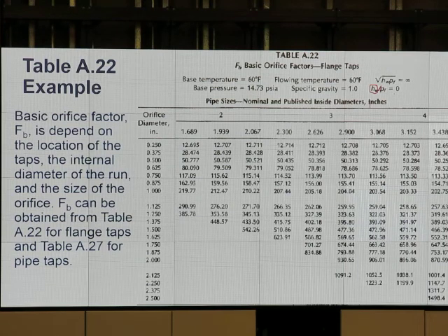It's not good. So this thing implies the pressure drop across the detector has to be a lot less than the static pressure itself. Okay? That's what I remember right now. I will also read it more and tell you. Okay? For right now, from what I remember is the HW has to be a lot less compared to the static pressure. Let's say I have a 100 psi A. I don't want the pressure drop like 50 psi A or something. The pressure drop has to be very small, like inch of water.